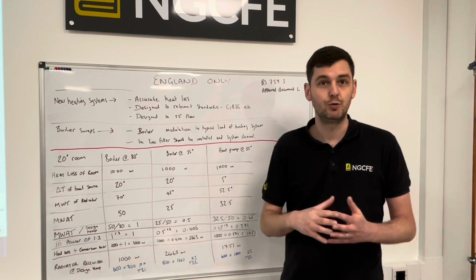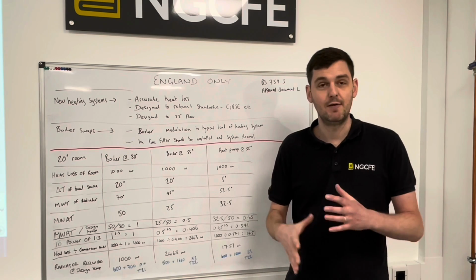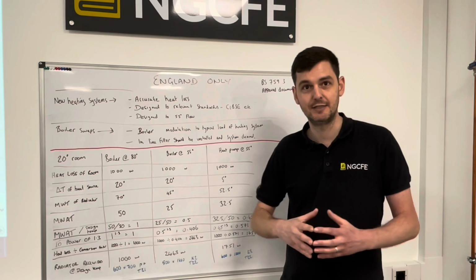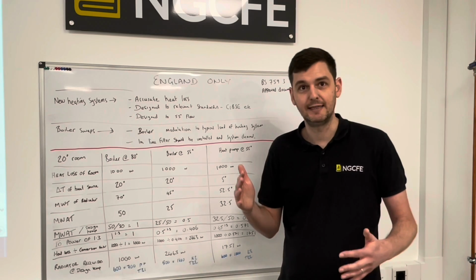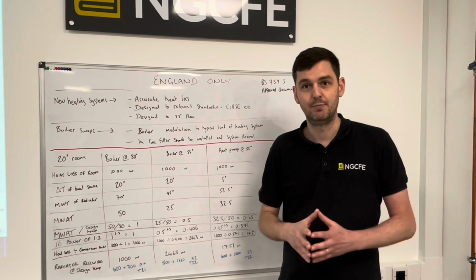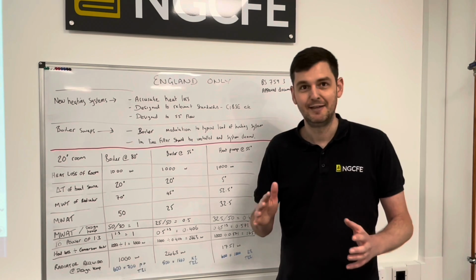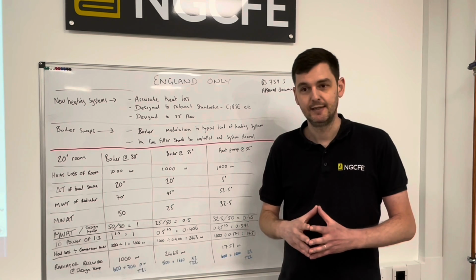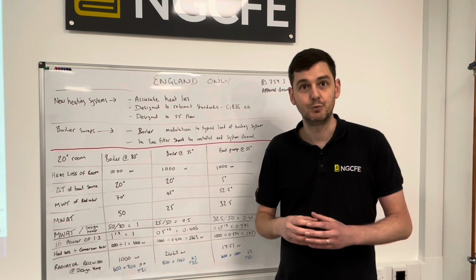With heat pumps, because they've got a lower DT, you also have to think about pipe sizing. However, it's not a massive issue. However, you do need to design systems correctly. Generally speaking, anything up to 9 kilowatts, you should be able to get away with 22mm supplies, or primaries if you like. Microbore, you really need to be careful of anything off microbore really. But yeah, pipe sizing, we need to think about that with heat pumps a lot more.